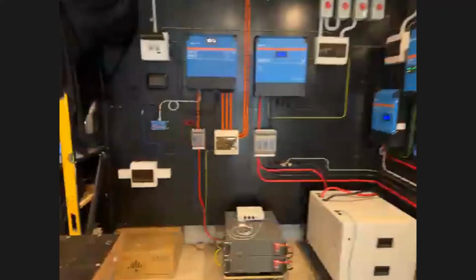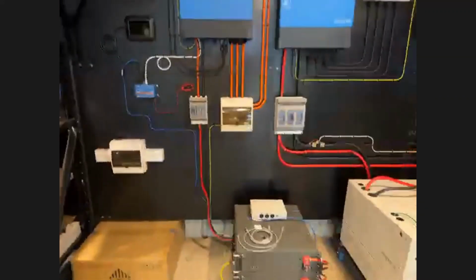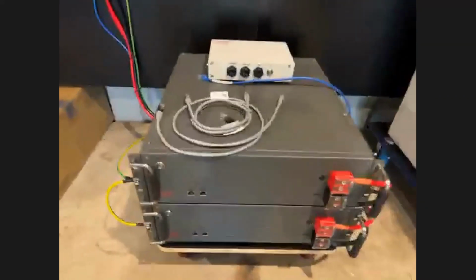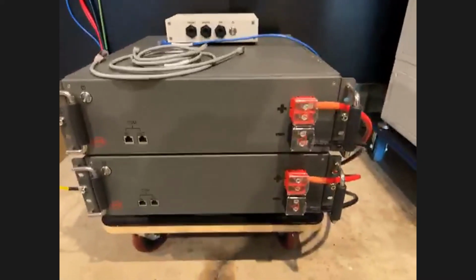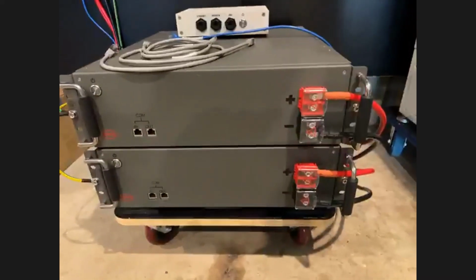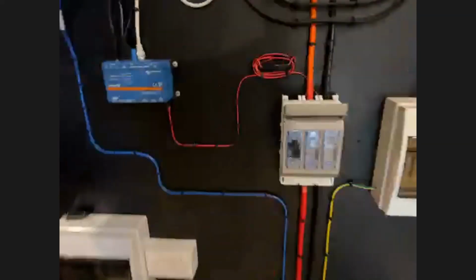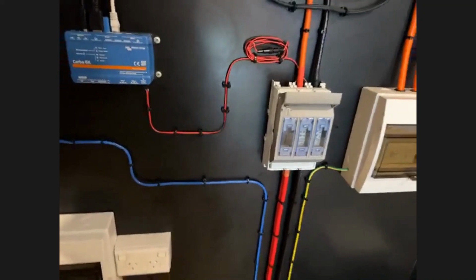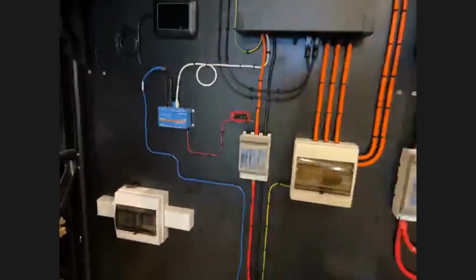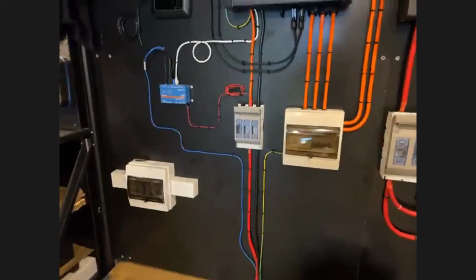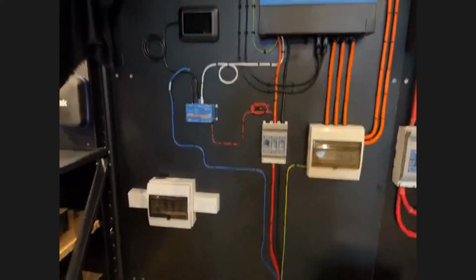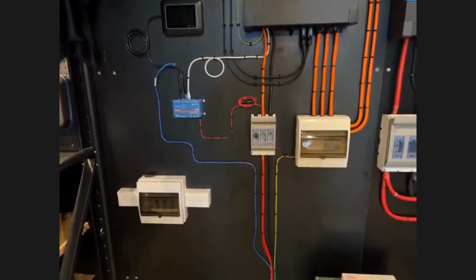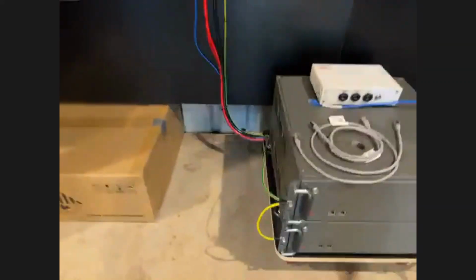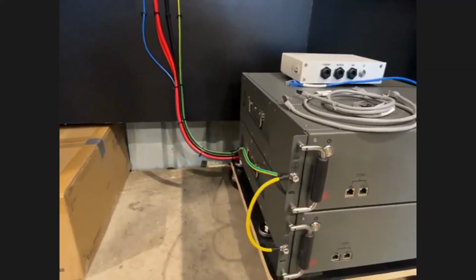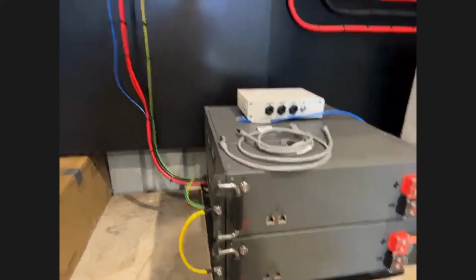Coming into the workshop here, you can see the batteries down here, currently not connected. They've been wired in, so I've got the battery power cables connected through. This is a test system, so don't follow my wiring here for any reason. This is functional wiring. You'll need to do your own wiring in compliance with local guidelines to make sure it's suitably compliant, but for this test installation, this will be functionally correct. We've got the batteries here connected through to earth on the chassis, just there.